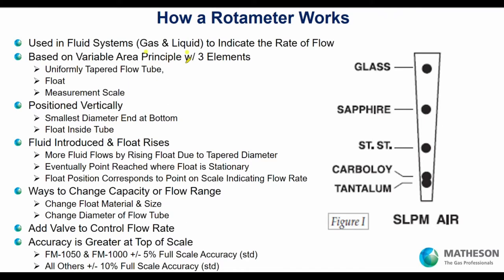Rotameters work on the variable area principle. It's comprised of three elements: a uniformly tapered tube — here's that taper, this is an example of a rotameter — the float, and the scale. The float can be several materials: tantalum, carboloy, stainless steel, sapphire, or glass — all common float materials. The scale will either be direct read, such as 0 to 10 liters per minute for air, or it could use a reference chart where you hit the hash mark on the tube and correlate that to a flow rate on a reference chart.